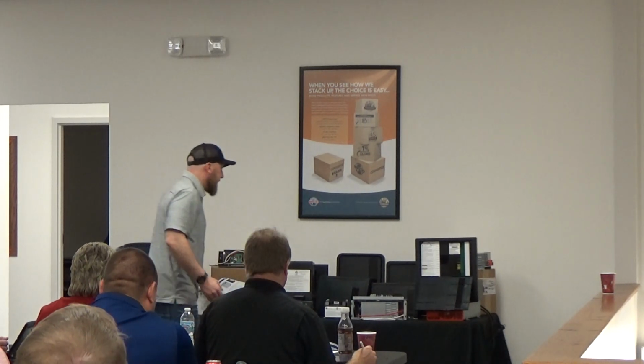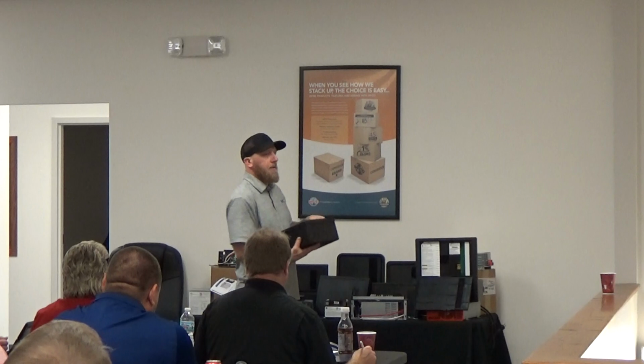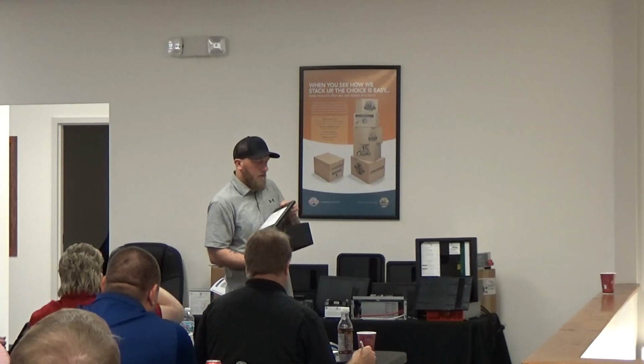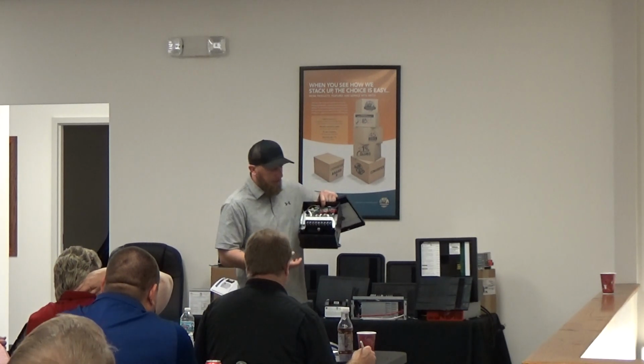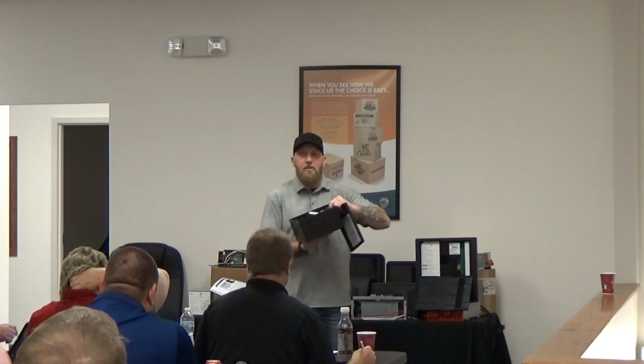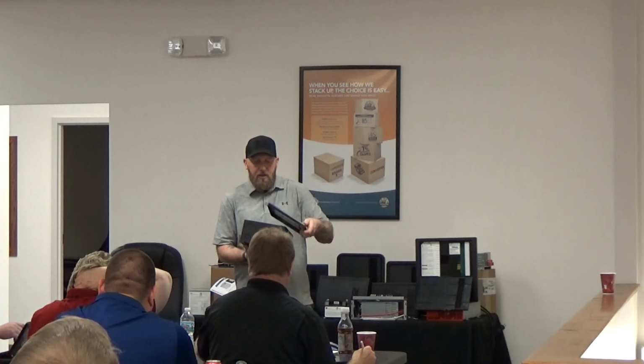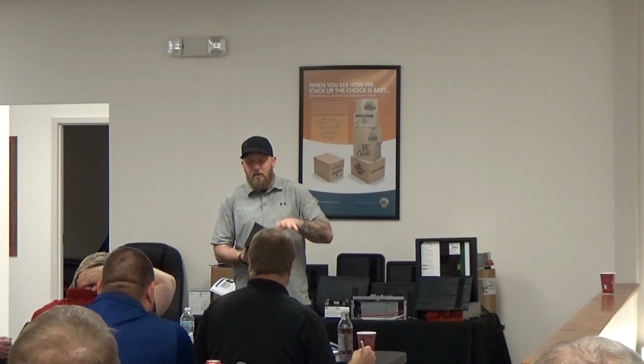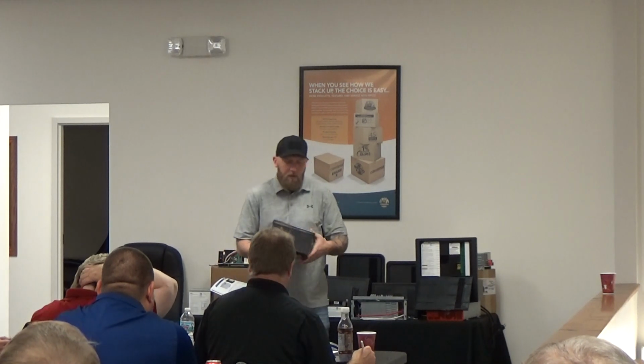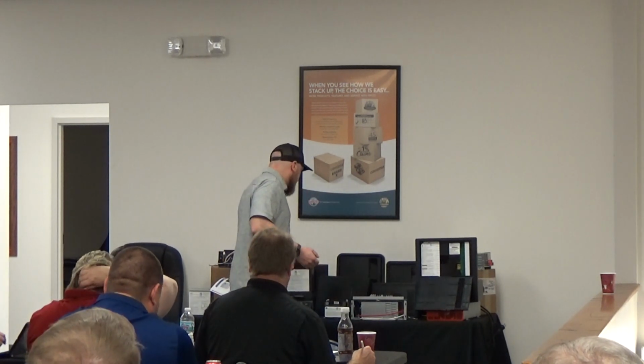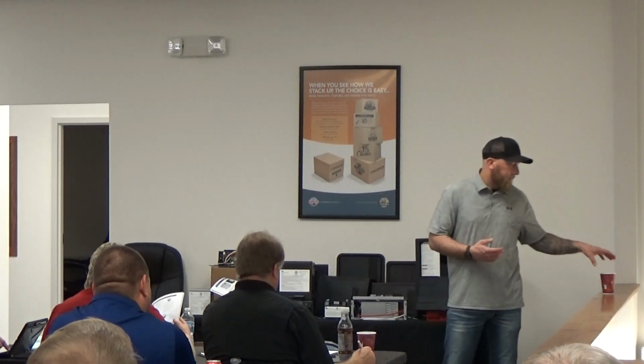This is our 30-amp transfer switch, so it's one leg of 110. The only difference with our T57, our 50-amp transfer switch, is you've got 2 legs of 110—L1 and L2 instead of just L1. But they're identical with the relay and can have the same issues. One thing they can't do is generate more power than they're given—they can only pass through what they're given.